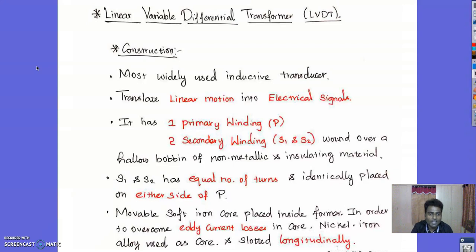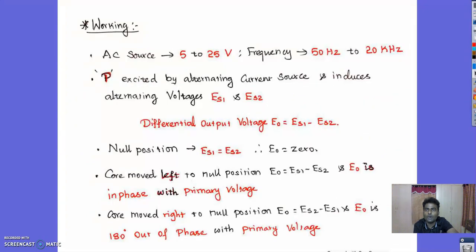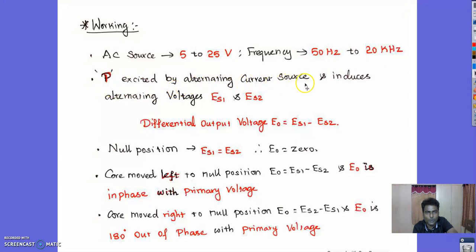The movable soft iron core is placed in the former to overcome eddy current loss. The core is made of nickel-iron alloy and is slotted longitudinally. The primary winding is wound in the center and secondary windings are wound on either side of the primary winding. For the working of the LVDT, an AC source of 5 V to 25 V and frequency from 50 Hz to 20 kHz is applied to the primary winding, which excites it and induces alternating voltages ES1 and ES2 in the secondary windings.